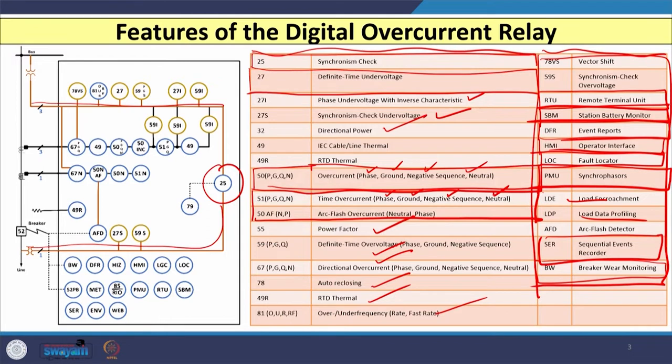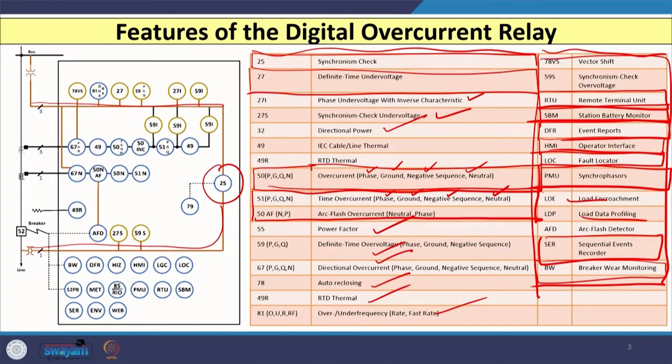So, we can say that along with all these optional features, which are compatible with reference to either IEC 61850 or maybe the IEEE C37.118 standard, which is for PMUs, these are also available with this relay. Along with this, some communication capabilities are also there. It supports communication facilities like the TCP/IP protocol, or maybe Modbus communication, or some other type of communication, SNTP and so on. So, these types of features are also available in this digital relay.